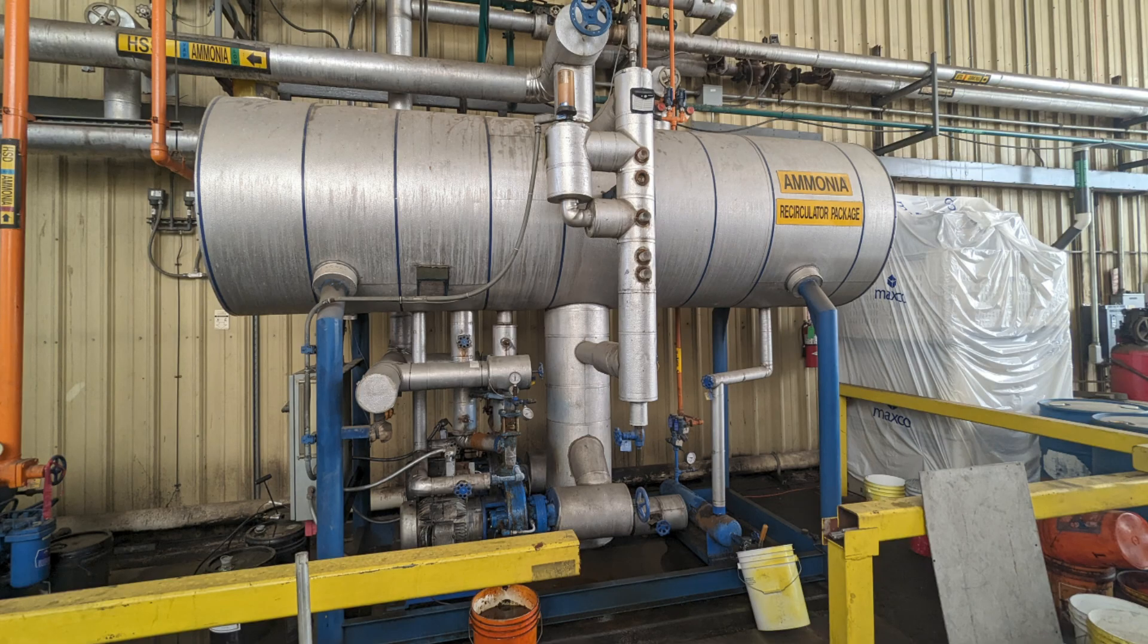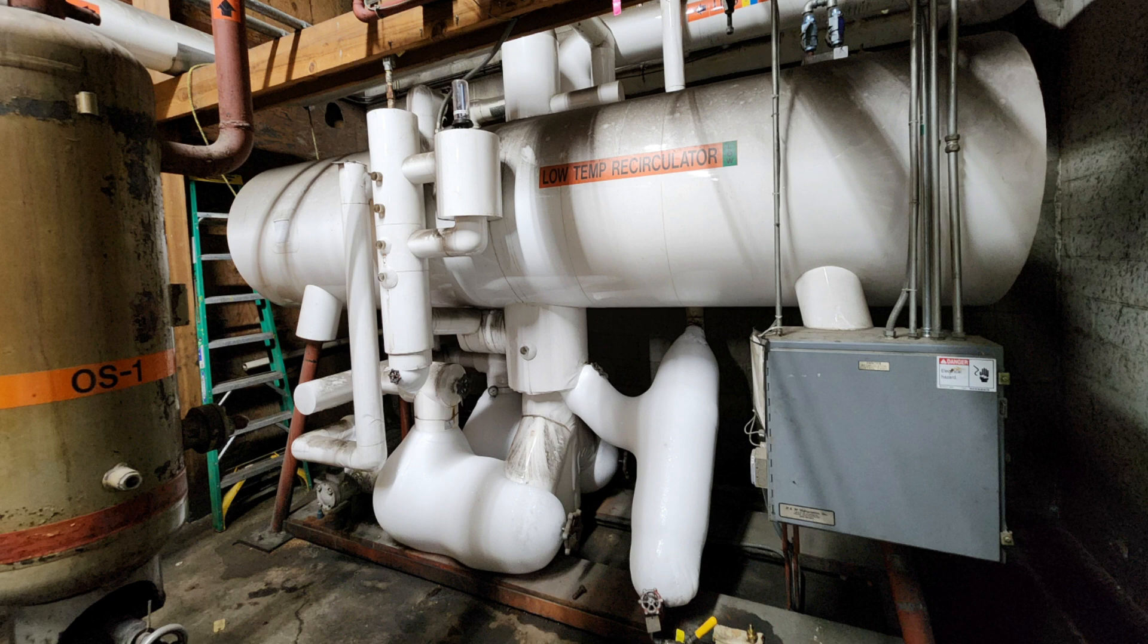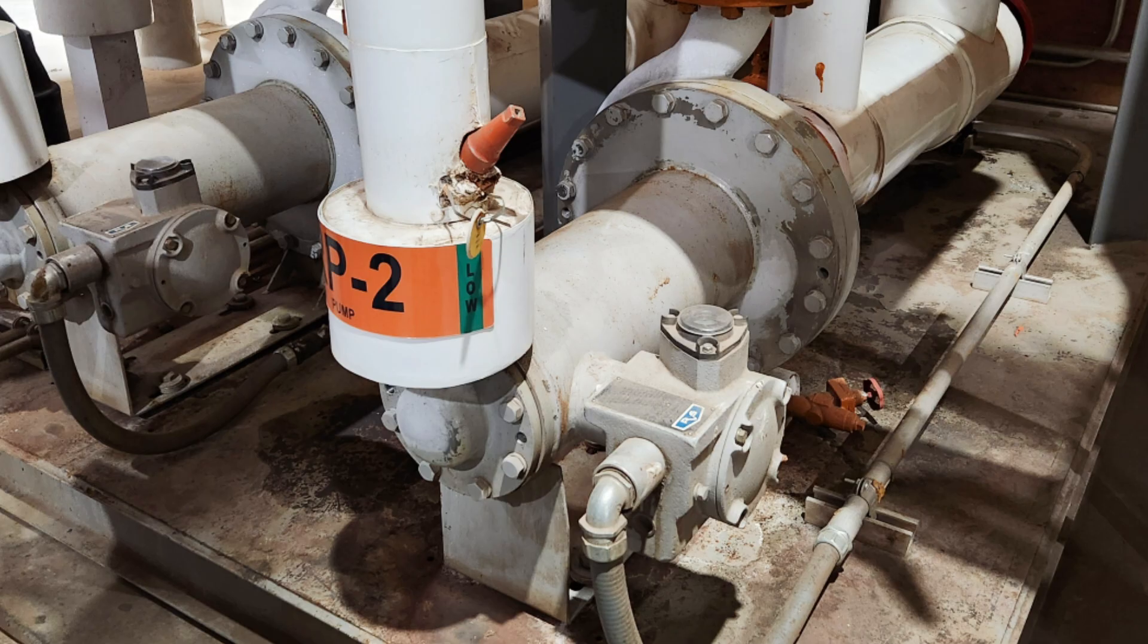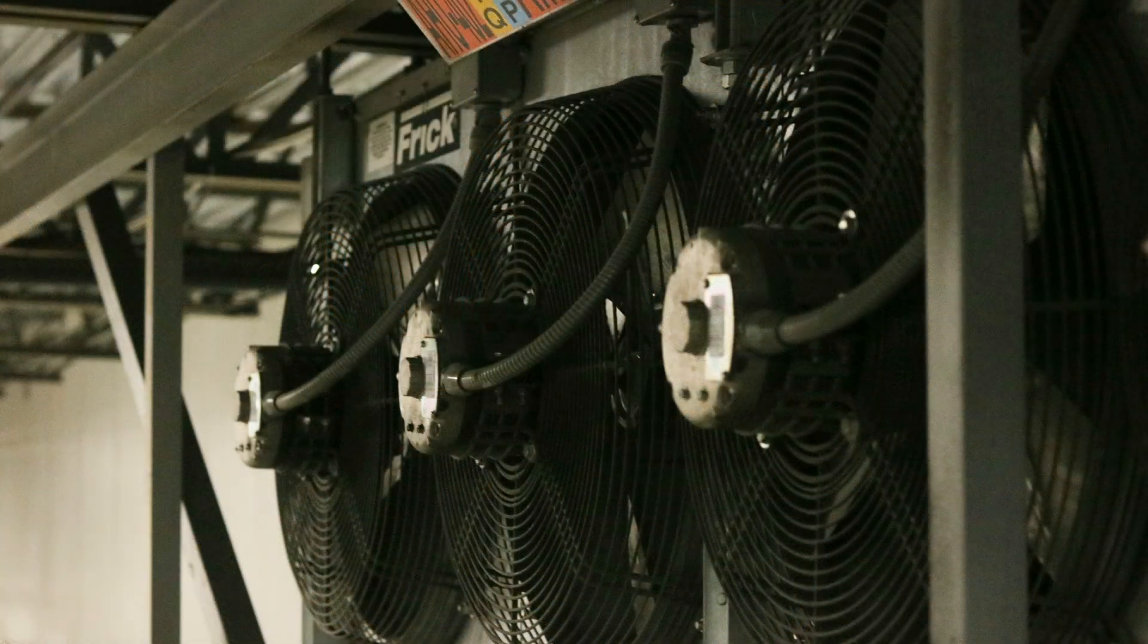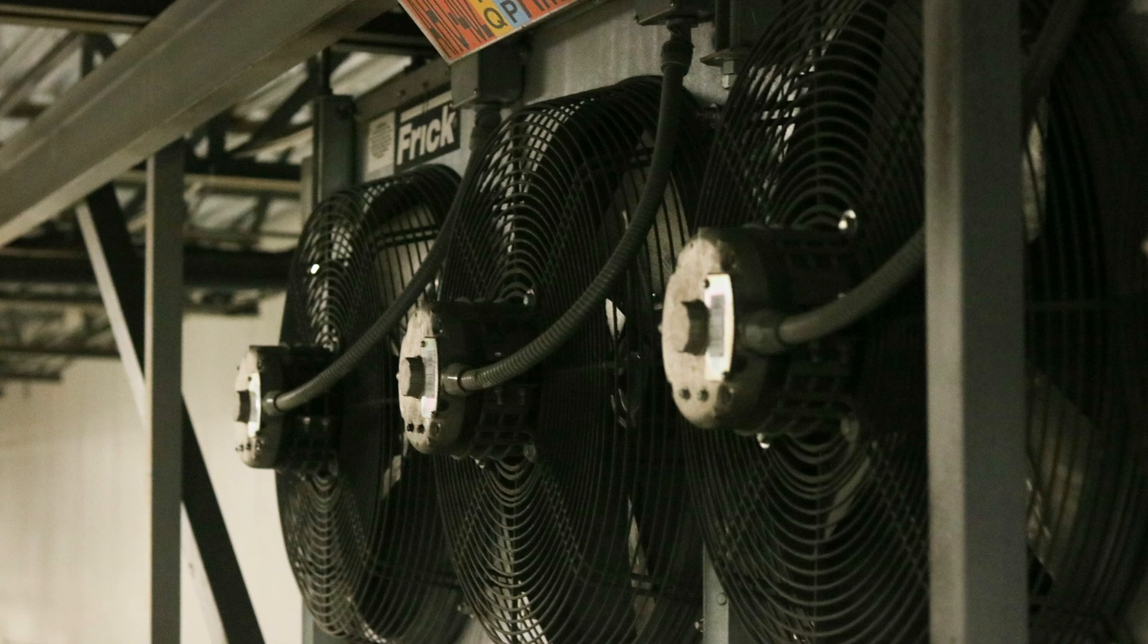In fact, the recirculator may be a long distance from the evaporator. Instead of using gravity to supply liquid to each evaporator, the recirculator will have a pump connected to the bottom of the vessel, which will move the cold liquid refrigerant from the recirculator to the evaporator.